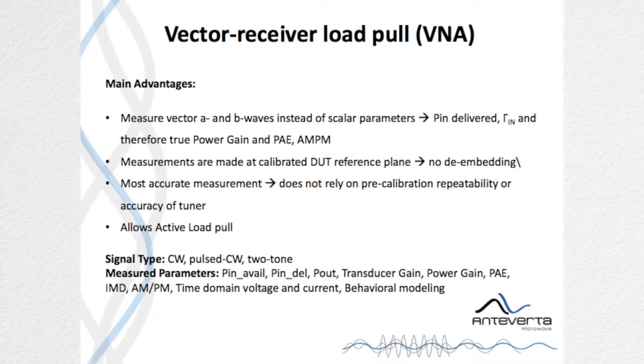The main advantage of a system like this is that you're now measuring a vector quantity, which allows you to measure actual input delivered power and gamma in, and therefore also measurements like AM/PM, PAE, and so on. The measurements are calibrated directly to the DUT reference plane, so there's no calibration required of the tuner itself, or at least the accuracy doesn't rely on the calibration of the tuner. And this makes for the most accurate measurements.